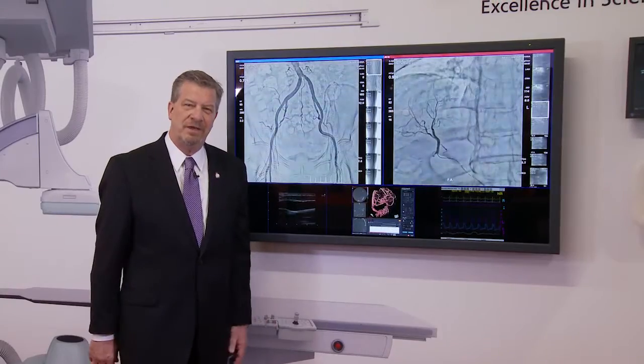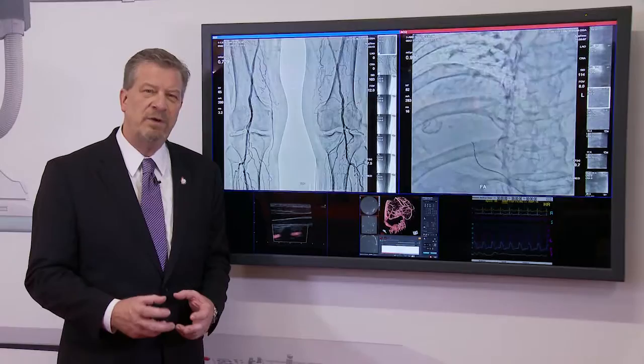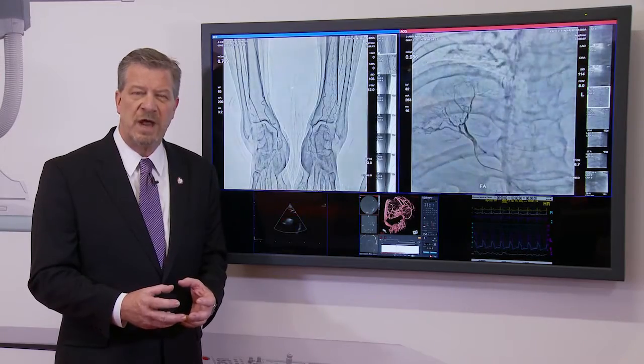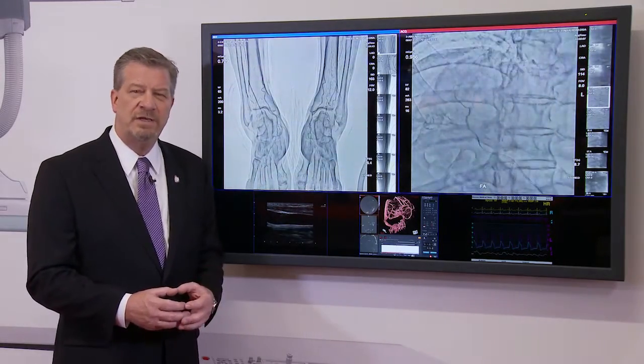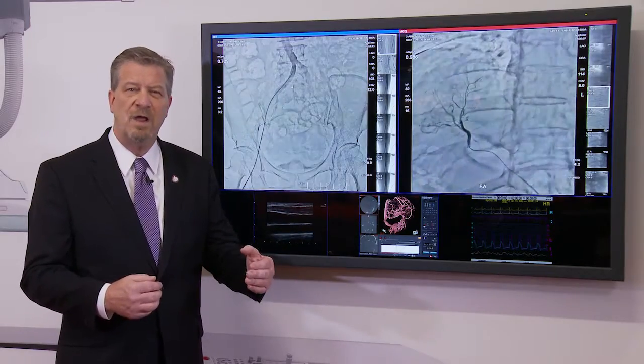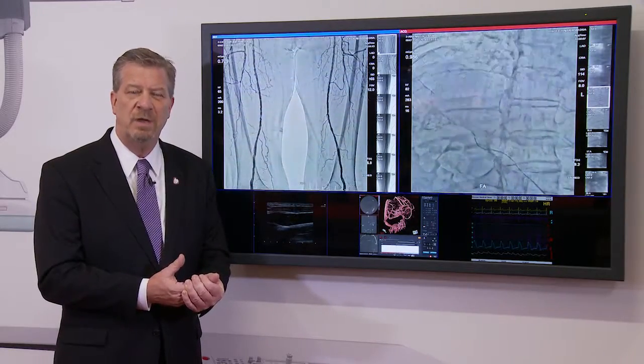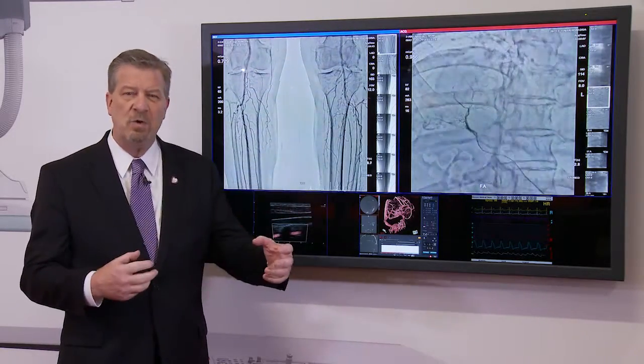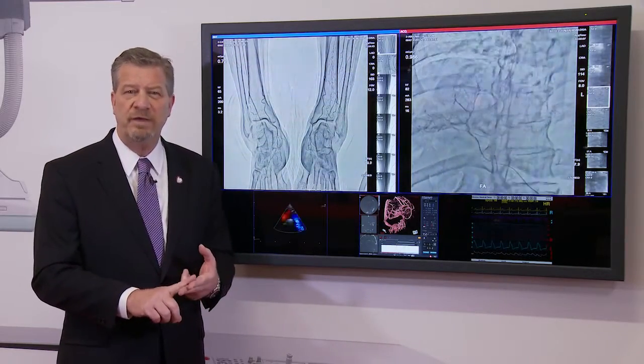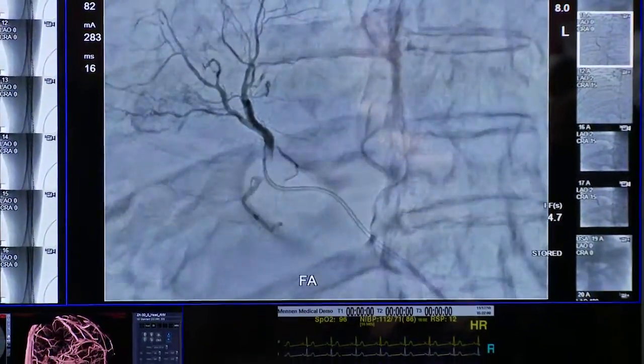Another feature of the Shimadzu Trinias system is a function called RSM-DSA — real-time smooth masking digital subtraction angiography. It's basically motion correction subtraction. For peripheral angiography, you can inject the patient, acquire the images, and they're subtracted on the fly. So if the patient moves, it's automatically compensated so you see great images every time. You don't have to re-inject the patient and you don't have to re-acquire the study. This is also workable with two processes we call pendulum and precession, with both the floor-mounted and ceiling-mounted positioners on all abdominal work.